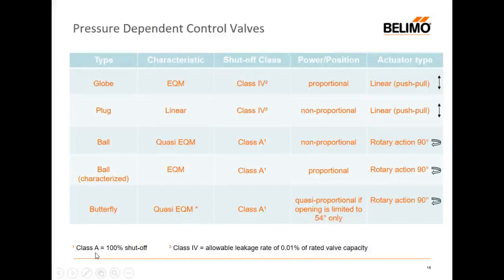Just for your reference, class A shutoff designates a valve which shuts off at 100%. There is no leakage. Class 4 valves, sometimes seen as class 5, have an allowable leakage rate, which is related to the size and the flow capacity of the valve. And they are allowed to leak a little bit of water in the closed position, which might not seem a lot, but they're also leaking something very important as well. They're leaking pressure, and we're looking for rises in pressure as the valves close to tell the DP sensor to signal the pump that the demand is reducing. We need to control the pump nicely. So having an allowable leakage rate might not look very harmful, but it can actually affect the control of the system. And certainly we don't want to waste energy if we don't have to.